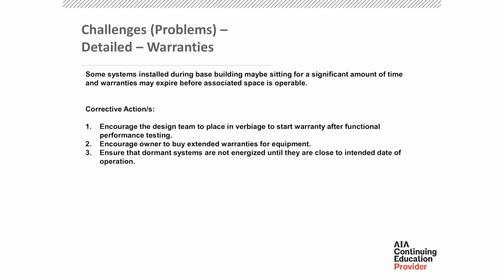Some systems that start during base building may be sitting for a significant amount of time, and warranties expire before the associated operation. So for corrective actions, and we've done this several times on other projects, encourage the design team to place verbiage in the warranty that it starts after functional performance testing is completed. It doesn't always happen, but you can have it in the specifications that the warranty starts once commissioning is completed. Encourage the owner to buy extended warranties for equipment. Ensure that dormant systems are not energized until they are close to the intended date of operation.